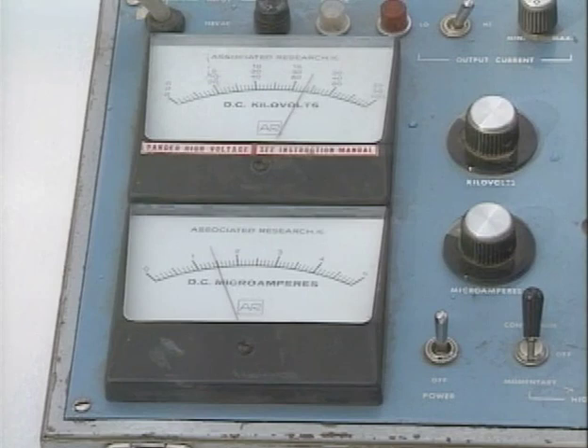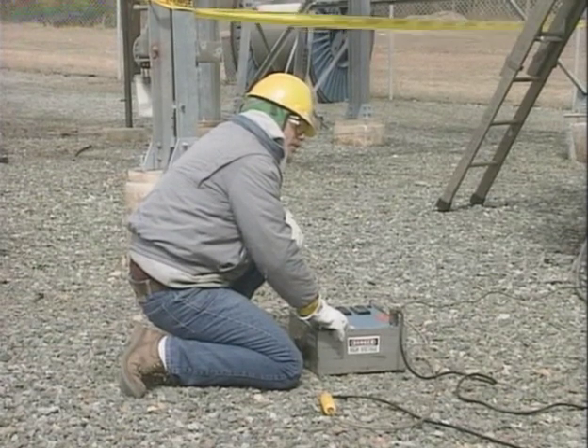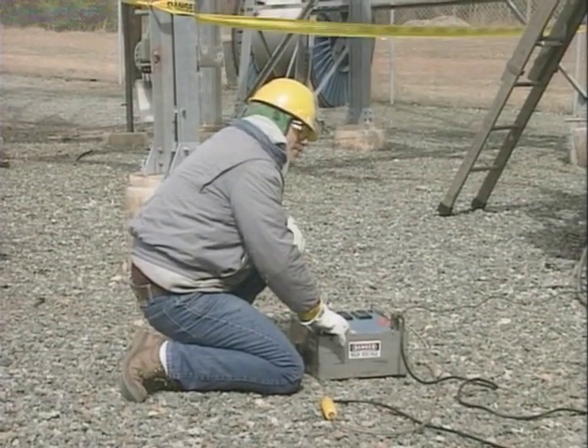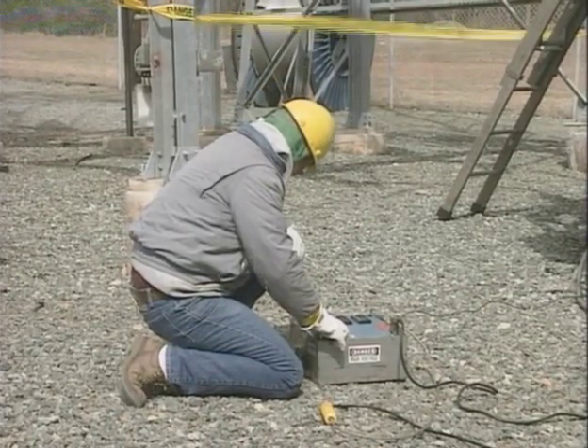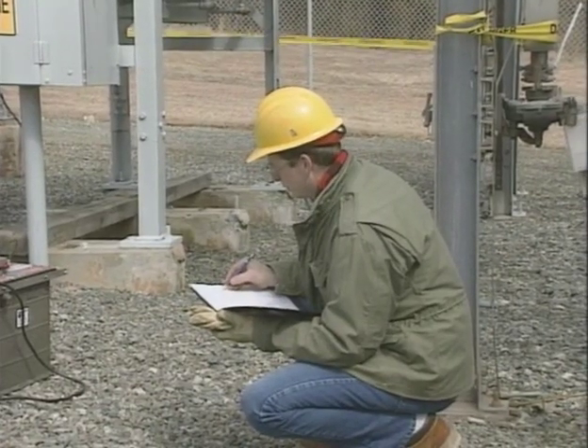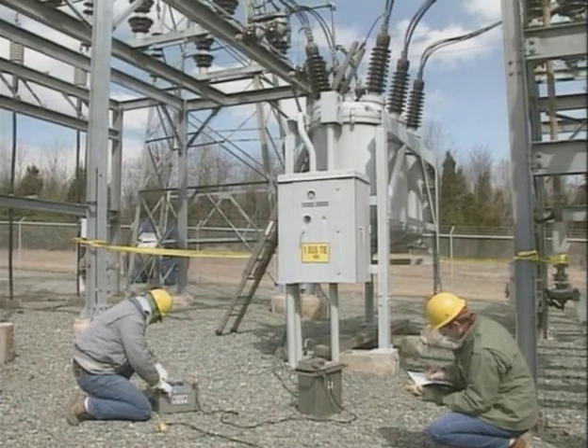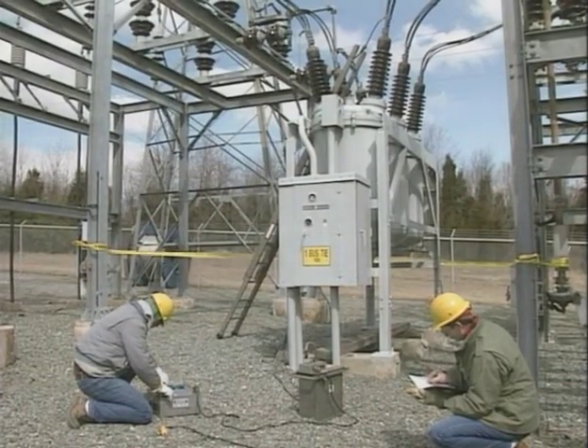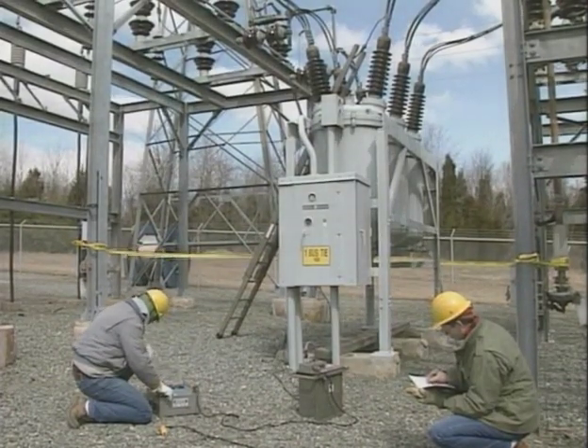If the circuit breaker insulation is weak, the stress of the applied rated voltage may result in a flashover or an insulation failure. If this happens, the test set automatically shuts itself off. If the test instrument indicates that leakage current exceeds an allowable level, the cause must be identified and corrected. If the insulation fails during the test, the failed components must be replaced.